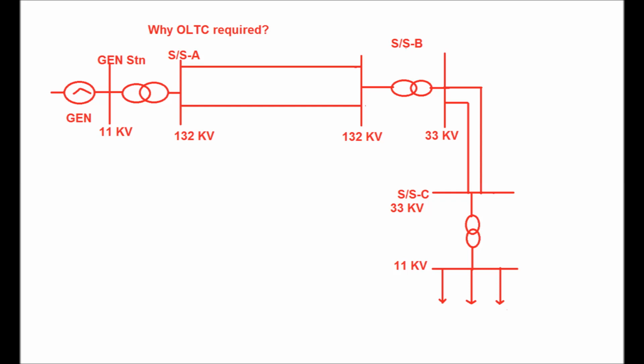and to transmit to the load end, it is further stepped up by means of a step up transformer, that is, an 11 kV by 132 kV power transformer. So from substation A end to substation B end, the power is transmitted through a 132 kV or any extra high voltage transmission line in order to minimize the losses of the transmission line. Again, at substation B end, the power is stepped down by means of a step down transformer, that is, a 132 by 33 kV transformer at substation B end. Then different 33 kV feeders are taken to the distribution substation, that is, substation C.